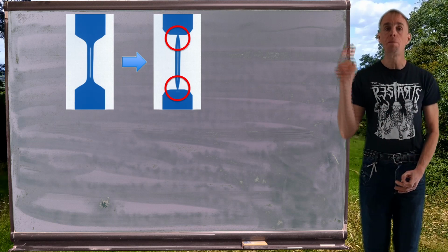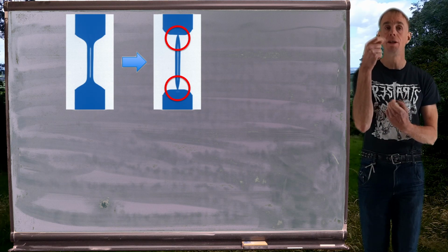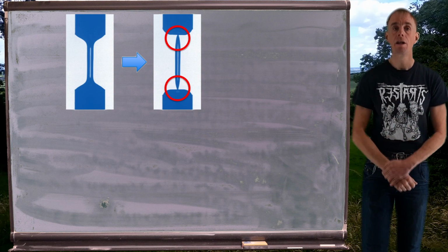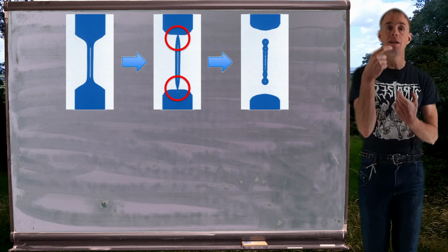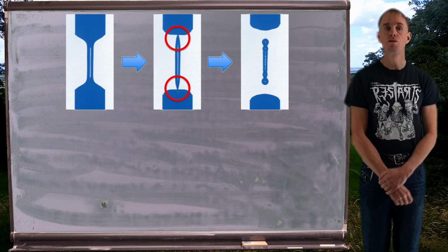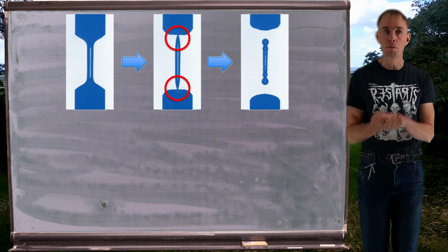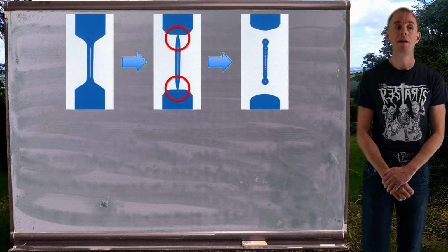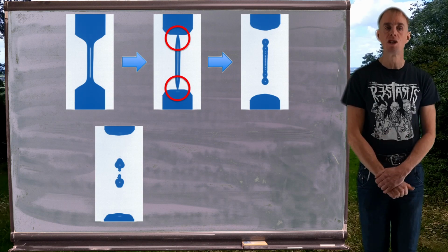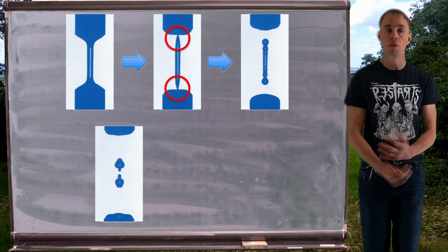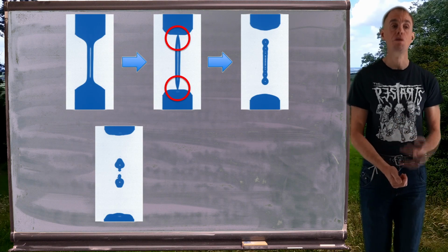But before the pistons have stopped moving, we can see that surface tension is pinching off that fluid filament at the top and at the bottom. If we look at the next key image, we can see that that fluid pinching has indeed resulted in a detached set of droplets. Note here the beautiful symmetry around the central axis, just showing how precise this instrument is. In the next image, we can again see a beautifully symmetric image of two droplets which have now broken up under the action of surface tension, and now the pistons have finally stopped moving.